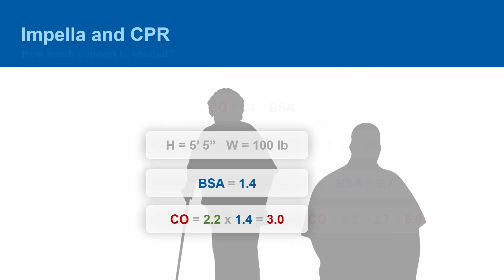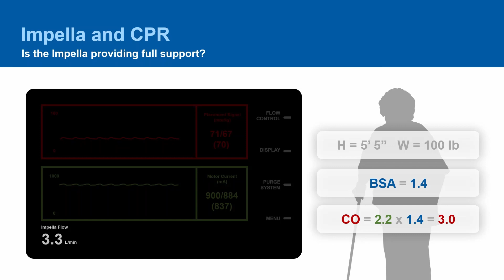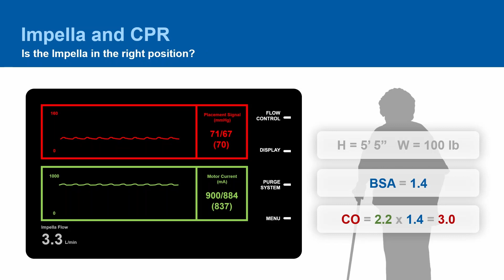In this hypothetical scenario, if the Impella was in a small patient with a BSA of, say, 1.4, they would need 3 liters of cardiac output to maintain a cardiac index of 2.2. Looking at the Impella monitor, we see that the cardiac output is 3.3. Thus, it should be providing sufficient cardiac output to perfuse the patient, even if their heart is not pumping at all.